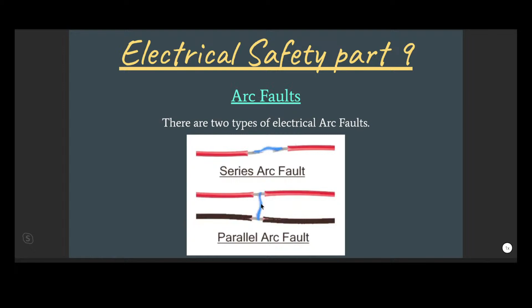But then we have a parallel arc fault. This might be where you have an extension cord that someone accidentally wasn't taking care of, and it's got a whole bunch of nicks and rips in the outside insulation. All of a sudden you can have a parallel arc fault. These are much more dangerous, and I've seen a lot of fires occur because of that. But the cool thing is we have these things called AFCIs - arc fault circuit interrupters. It has a little circuit board inside that senses if there's a parallel arc going, and it'll trip itself, not allowing the power to come back on until that's resolved.